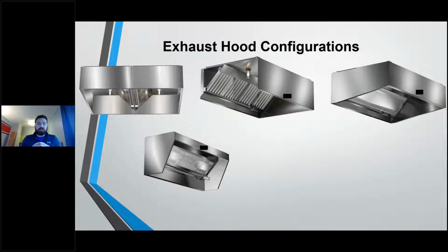The reason for that is these hoods are going to typically hang anywhere from 24 inches to 36 inches above the cooking surface. So not the 80 inches above the finished floor. They're going to be right above the cooking surface. And they're typically going to have some sort of an underhang requirement of anywhere from 6 to 18 inches, depending on the application. And since they sit so low and they have an underhang requirement, they don't have to hang at that 80 inches, like I mentioned.